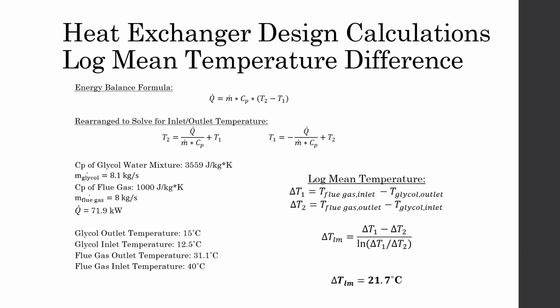This value was used as an accurate assumption of the Guelph stack mass flow rate. The temperature of the Guelph stack is known to be 40 degrees Celsius. Applying an energy balance formula allowed the inlet temperature of glycol and the outlet temperature of the flue gas to be calculated. With all inlet and outlet temperatures now known, the log mean temperature formula could then be applied. This yielded a log mean temperature difference of 21.7 degrees Celsius.